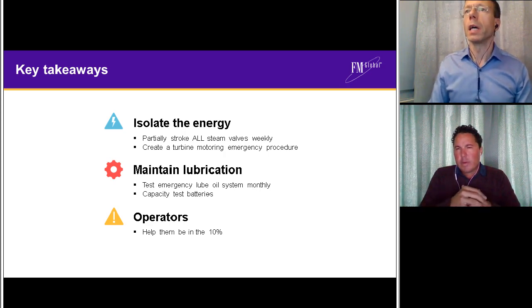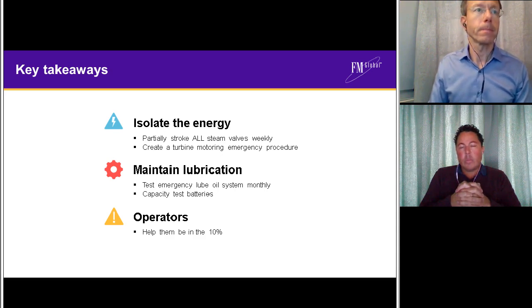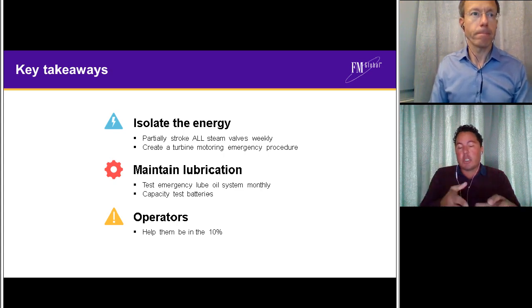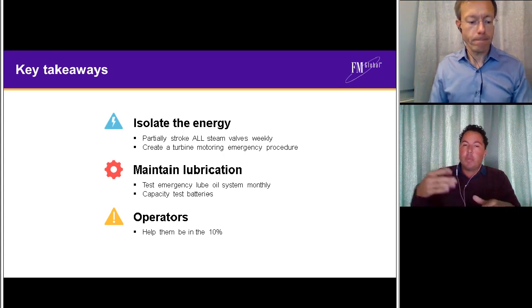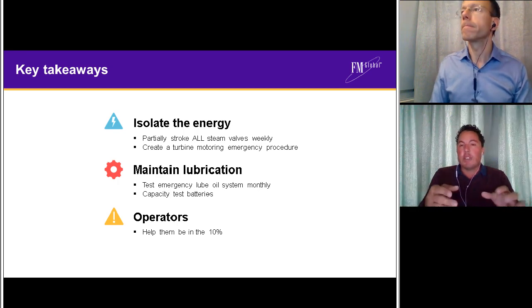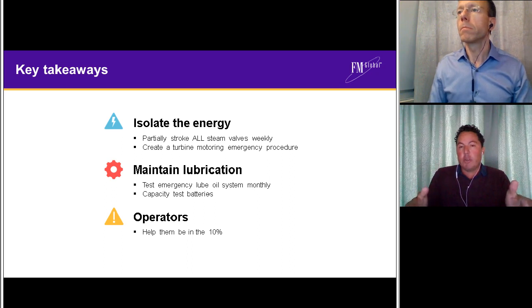Related to that, Uzair from the Hub Power Company says, can the DC lube oil pump discharge in the same header line to which our AC lube oil pump discharges? Yes, and that's generally what we find on site. It's discharging to the same line, but it's post the coolers and the filters. So effectively, all you've got is a length of pipe between your emergency lube oil pump and your point of consumption, your bearings.